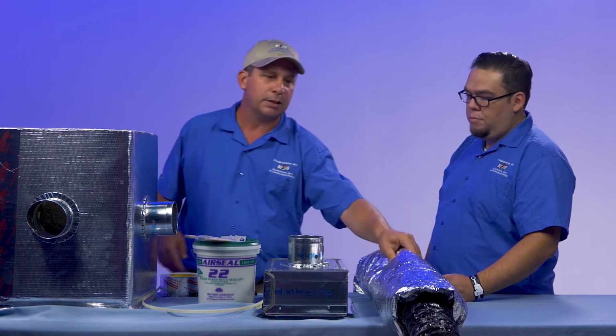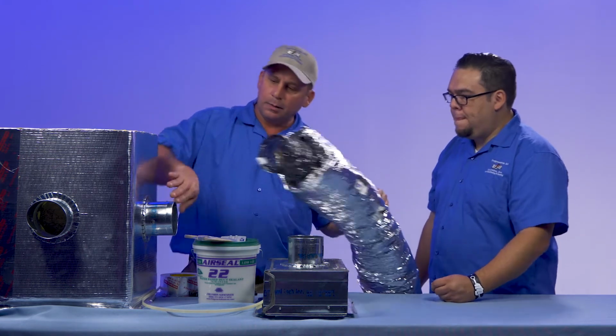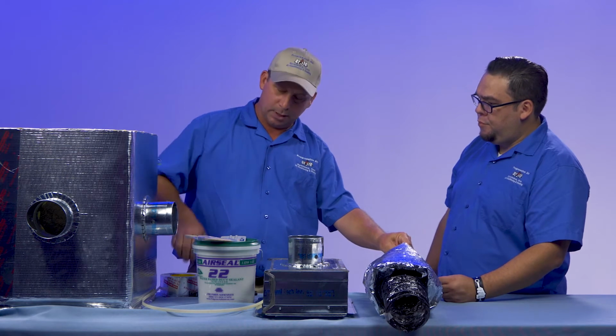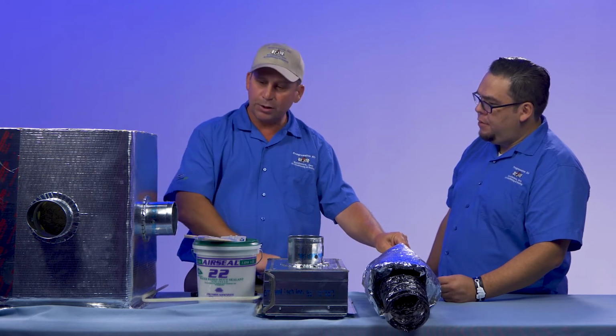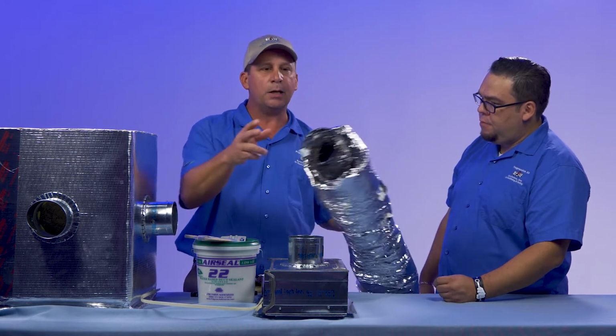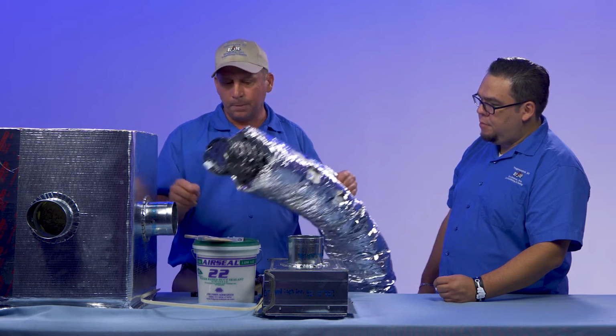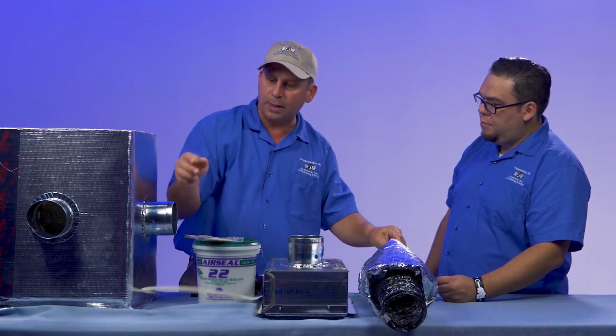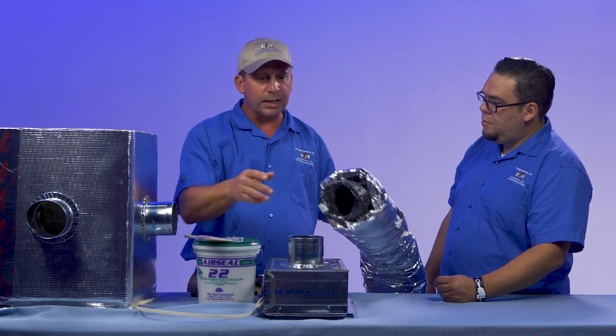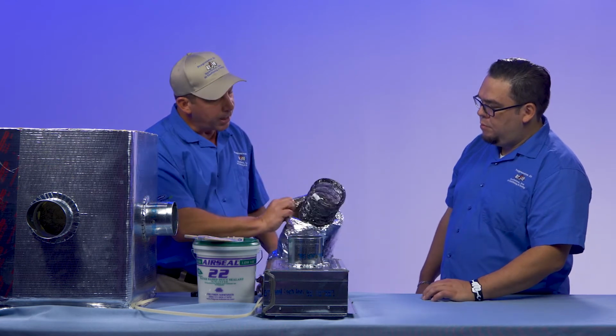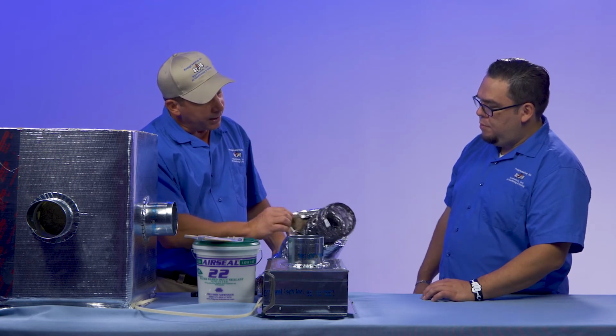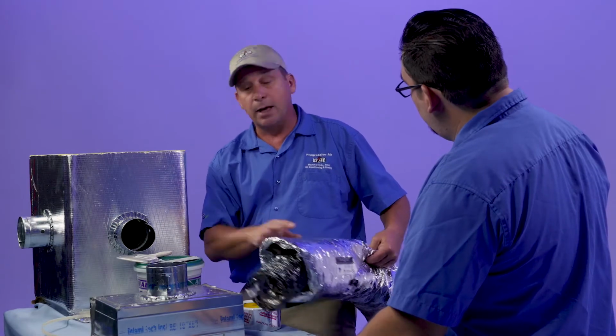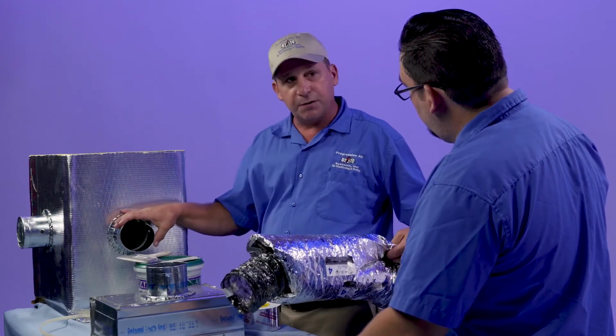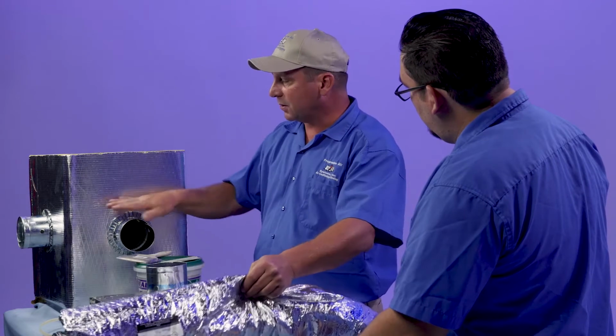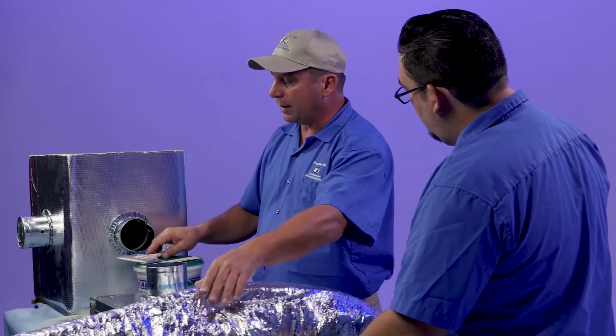So the ductwork would actually just go and connect into here. This collar right here would be taped with aluminum foil tape. Okay. So you don't have any air penetrating through the leaks here. You'd also attach this here along with a strap that would pinch in on here and secure it. And then you have an inner liner, the insulation, and then the outer liner. And that would just be fitted up here. Another strap would go on tight. We would also tape around that with aluminum foil, and then, of course, seal it.